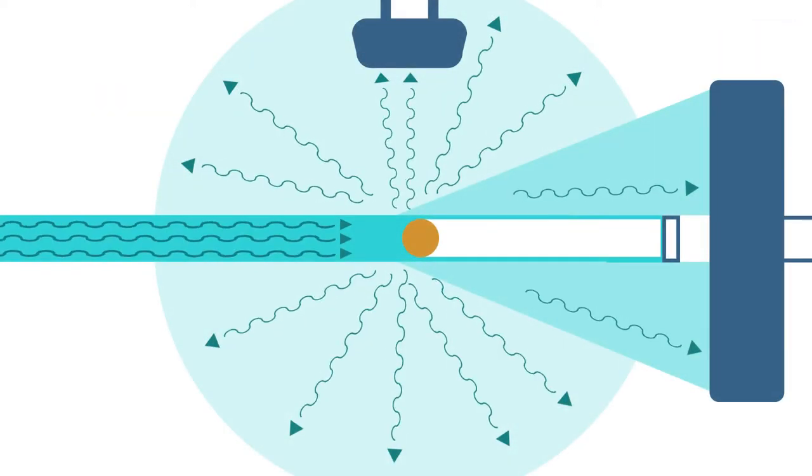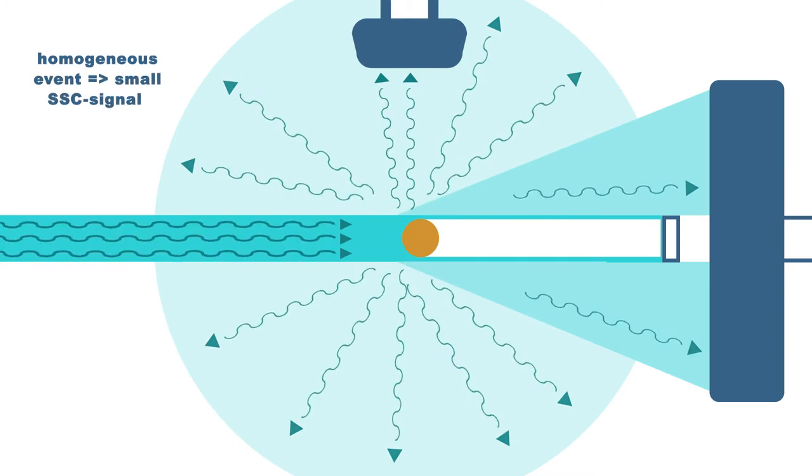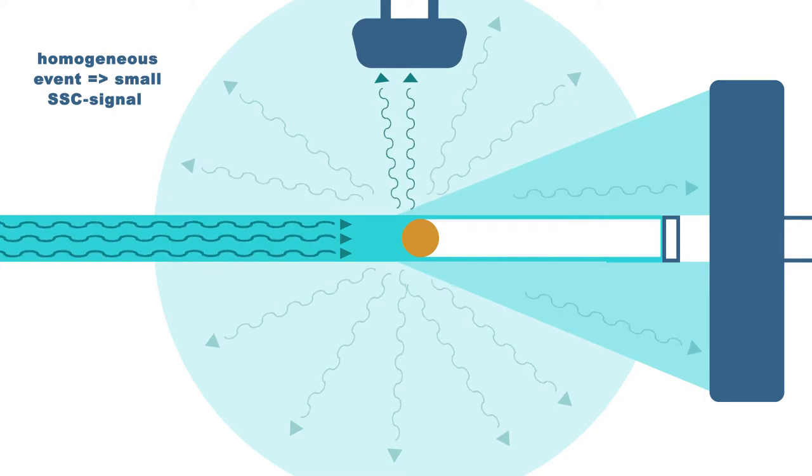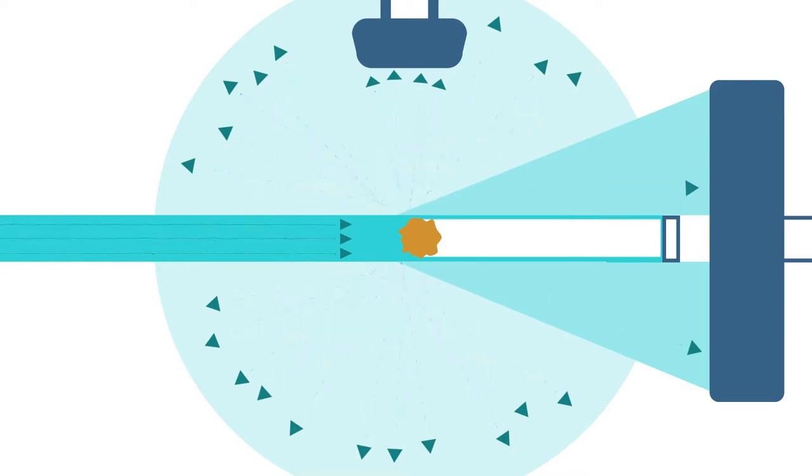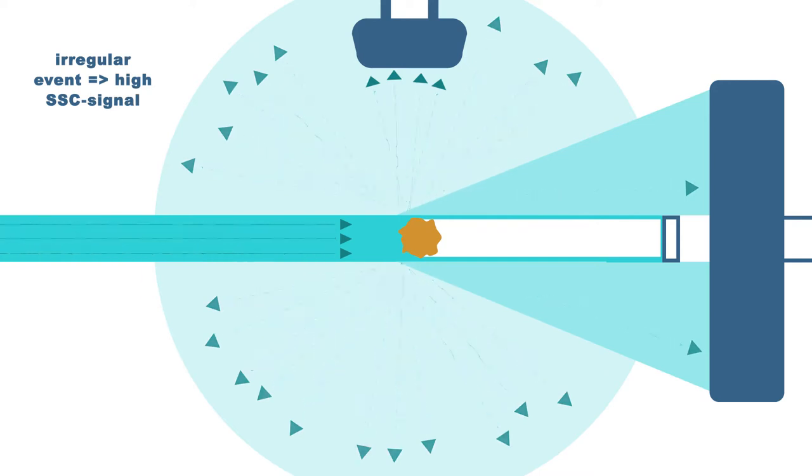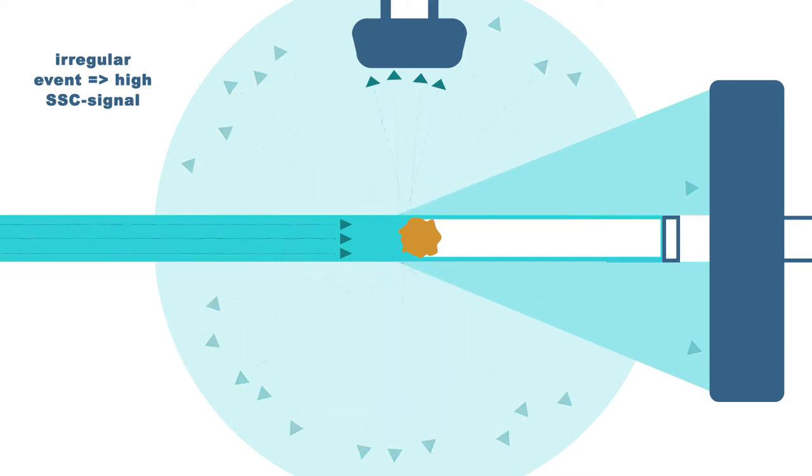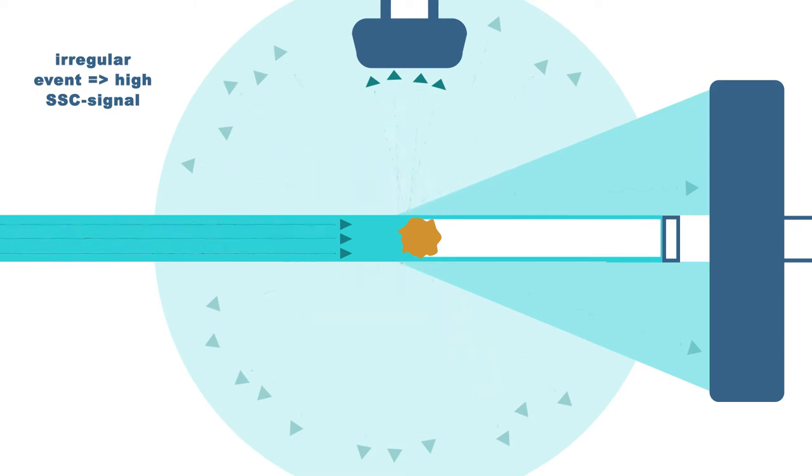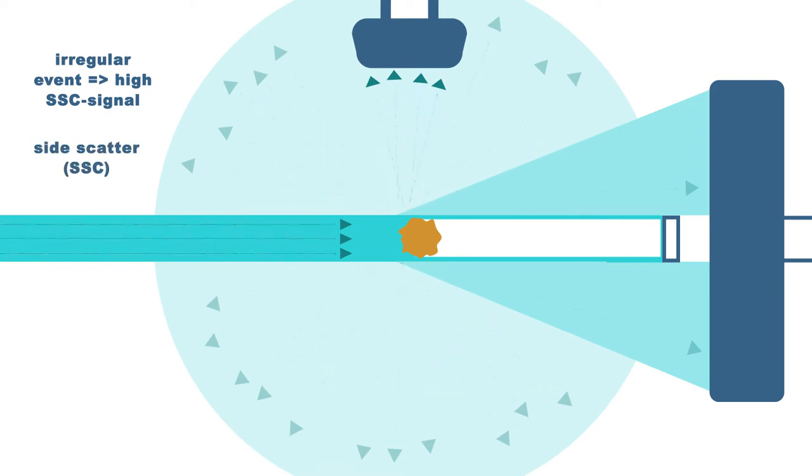If an event is homogeneous, both internally and externally, only a small signal for side scattered light will occur. There will be less diffraction and scattering interactions. In this case, less light intensity will reach an additional detector placed at a 90 degree angle to the laser beam. If the event is irregularly structured at its surface and inside, there will be strong diffraction and scattering interactions. However, the wavelength will be unaffected. In flow cytometry terminology, this signal is named side scatter. The abbreviation is SSC.